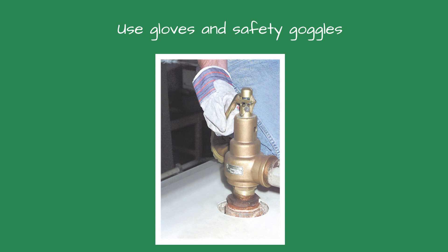Use safety goggles and gloves. I like to let it flow for five seconds before releasing the lever, then watch to make sure it stops. If it doesn't stop, try opening it again and blowing it off. If it still leaks after that, the safety valve should be replaced and the boiler should not be fired. The leaking could allow scale to form and change the relieving pressure of the pop safety valve.